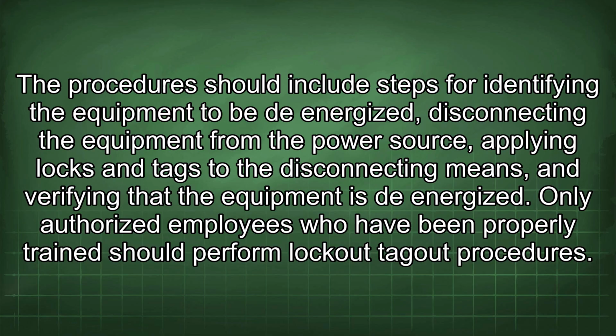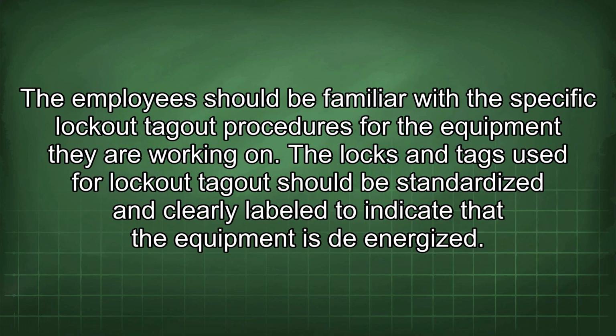The procedures should include steps for identifying the equipment to be de-energized, disconnecting the equipment from the power source, applying locks and tags to the disconnecting means, and verifying that the equipment is de-energized. Only authorized employees who have been properly trained should perform lockout-tagout procedures. The employee should be familiar with the specific lockout-tagout procedures for the equipment they are working on.